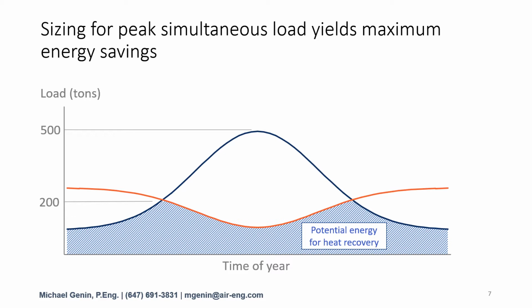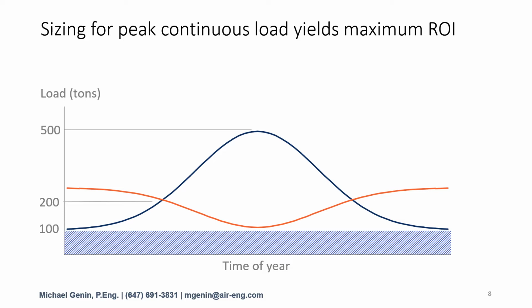The system would not always operate at full load, but it would have a larger capital cost. The energy savings would be the priority, and this would be the way to go. The total annual energy savings would depend on the exact load profile. However, if we wanted to size the chiller for the maximum ROI, then we would size the chiller for the maximum continuous load, 100 tons in this example.